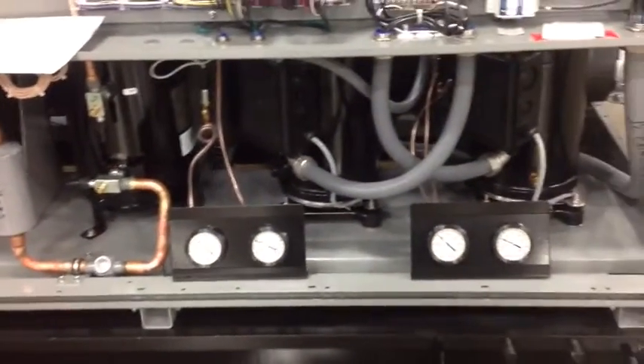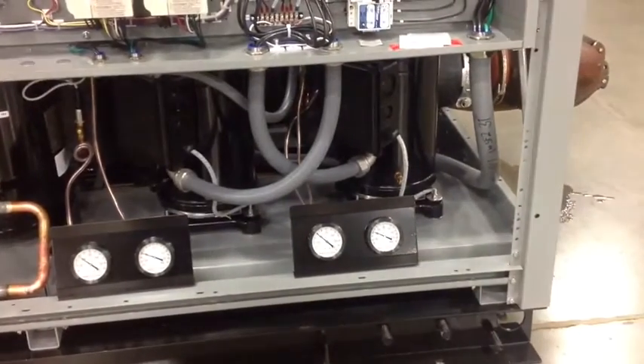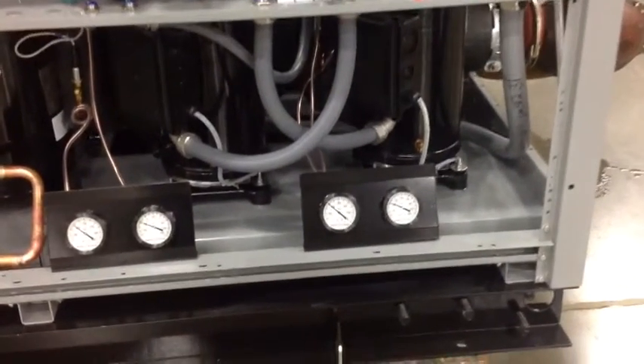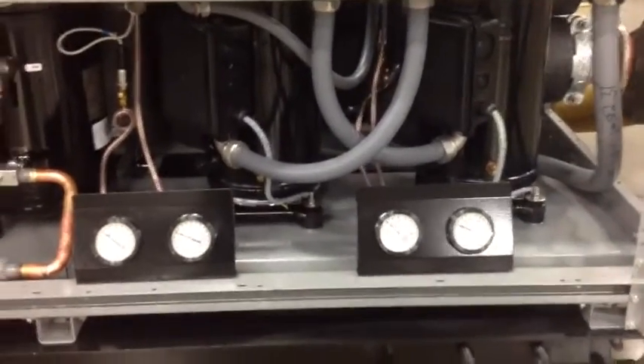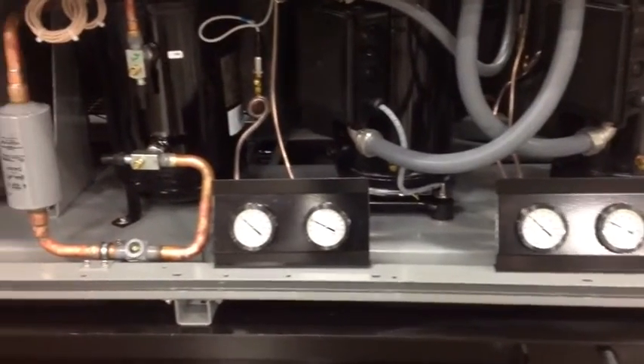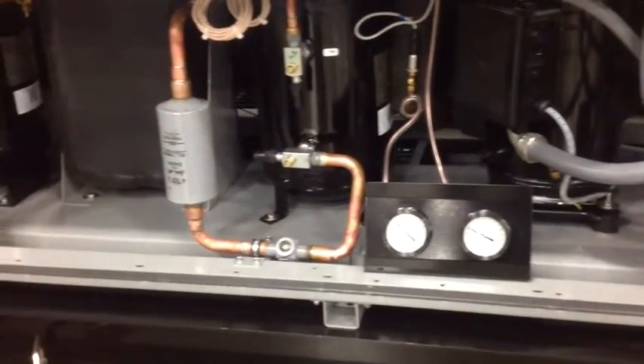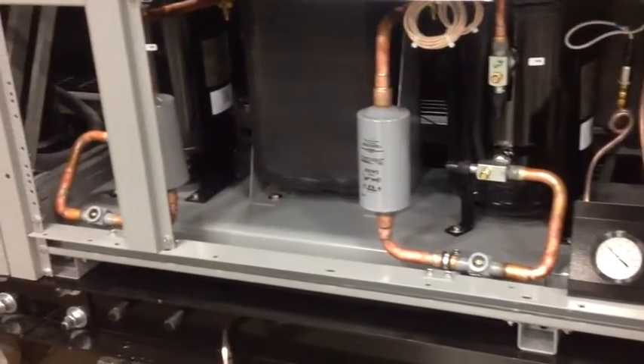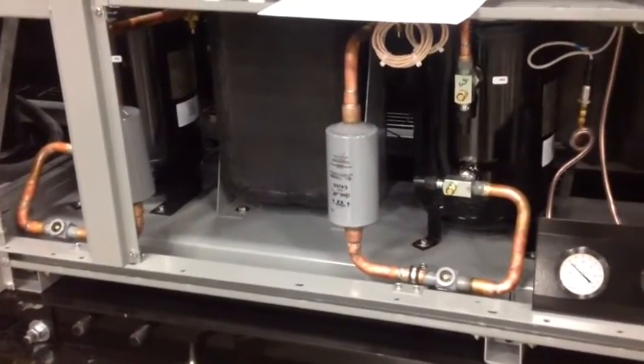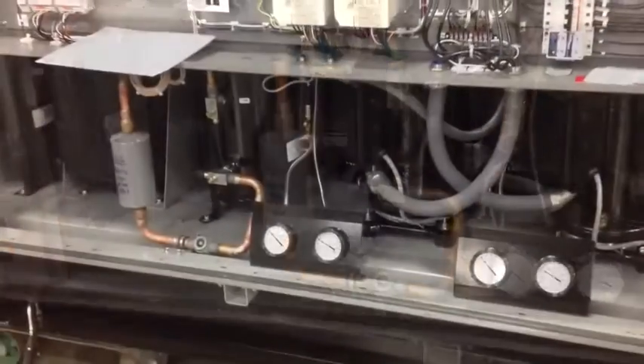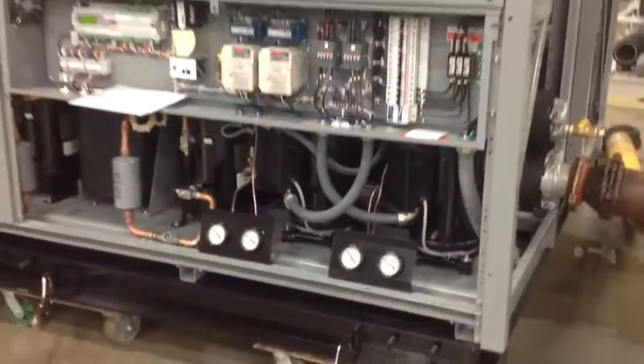And now we'll look at the lower components. You see a low pressure and high pressure gauge for each circuit. Again, there are 2 of them since this is an independent circuit chiller. You can see the liquid line filter dryer for circuit 1 and circuit 2, the evaporator in the background with the receiver on each side.